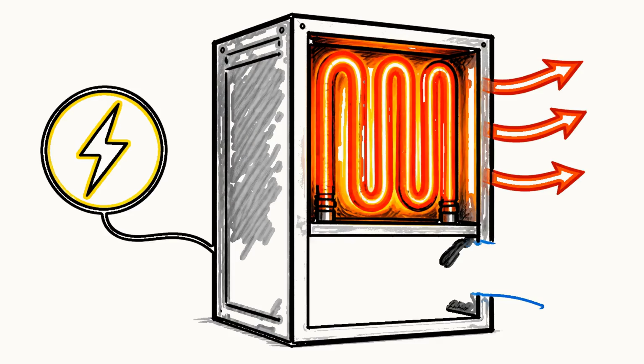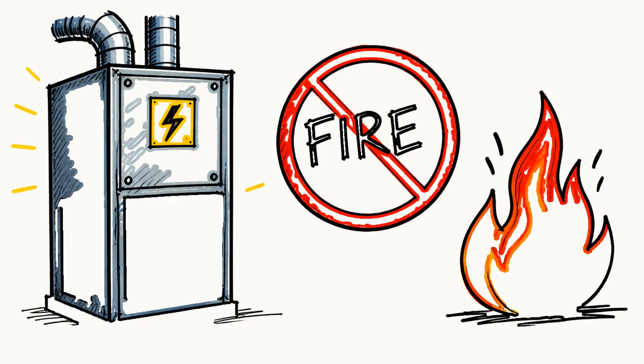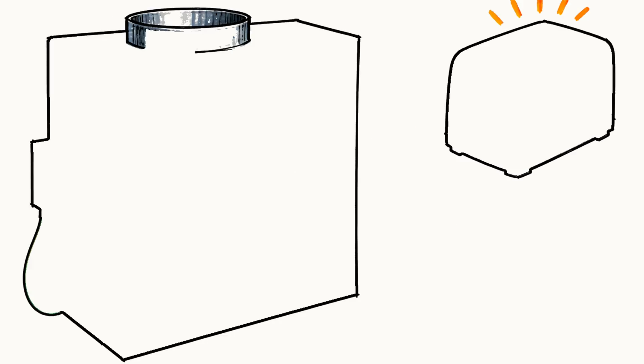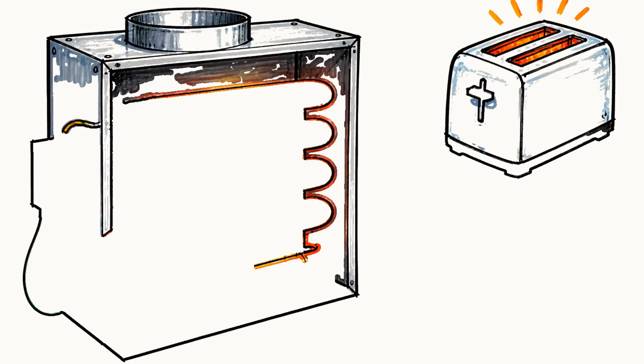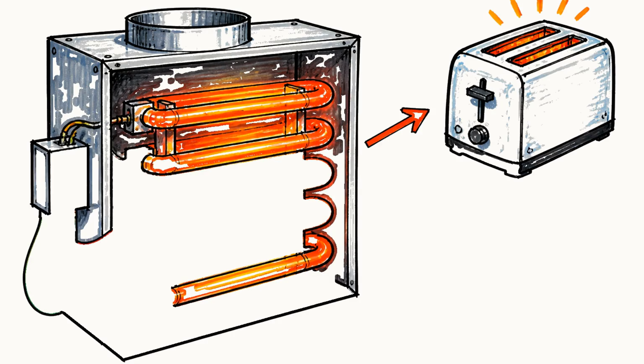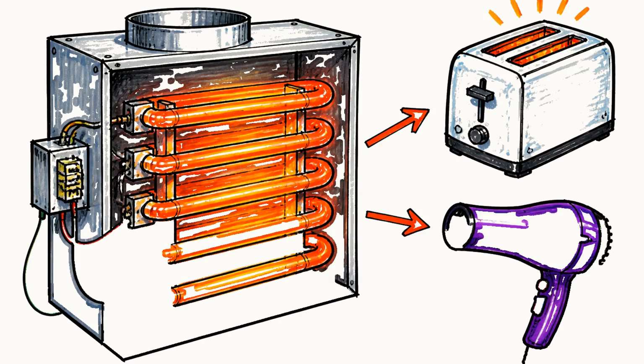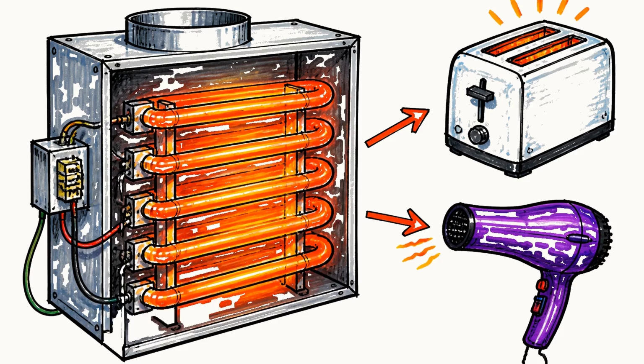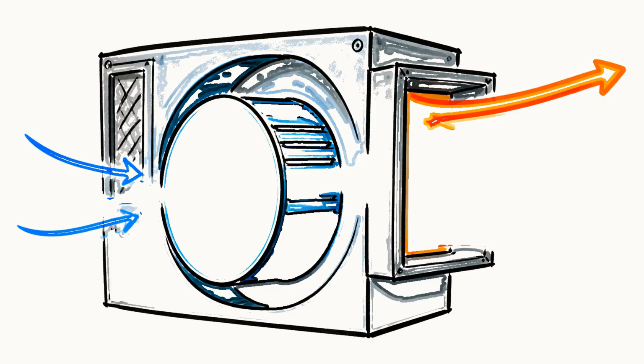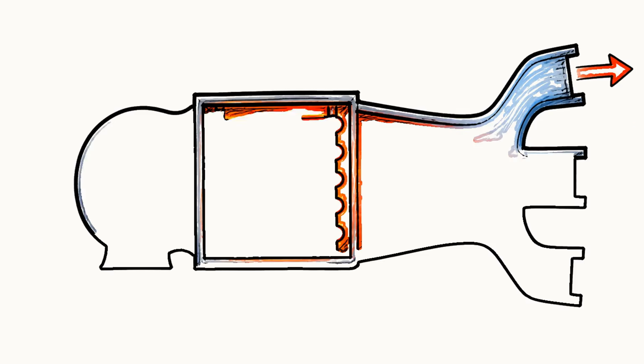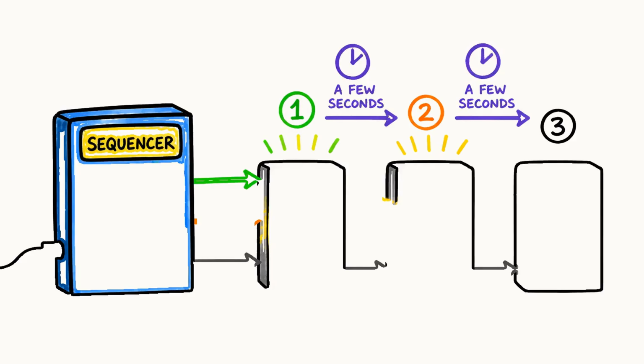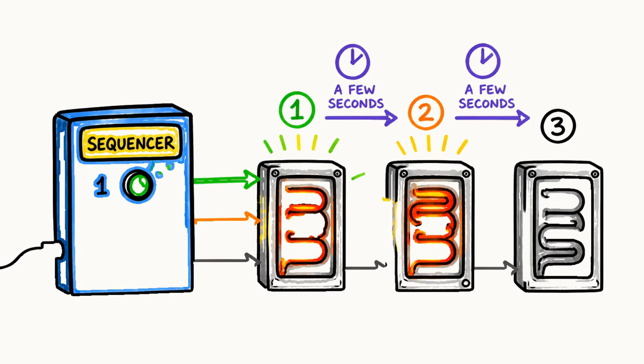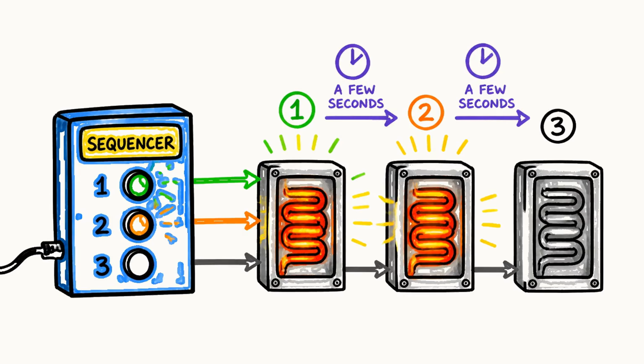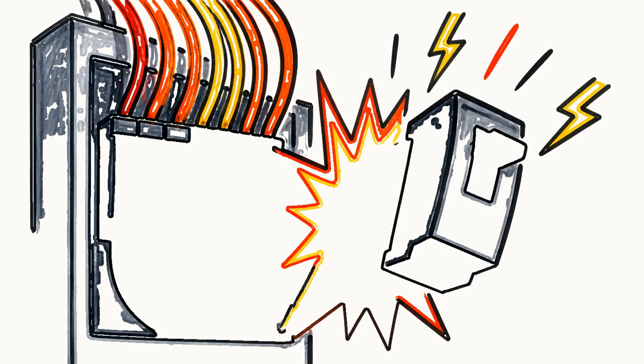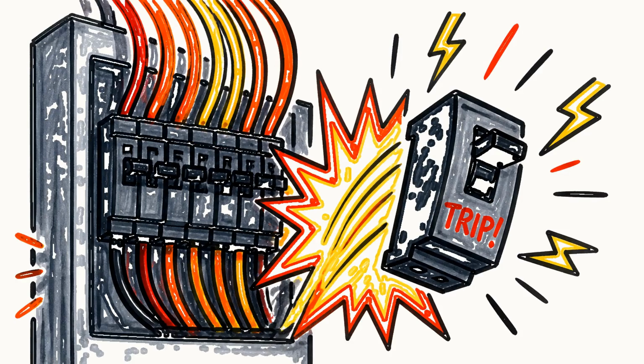Not every furnace burns gas, though. An electric furnace skips the fire entirely. Instead of burners and a heat exchanger, it uses thick metal coils that heat up when electricity runs through them, exactly like the elements in a toaster or a hairdryer, just much bigger. The blower still does the same job, pushing house air across the hot coils and out to the rooms. The clever part is a piece called the sequencer, which switches those coils on one at a time a few seconds apart rather than all at once. If they all fired together, they would yank so much power that they would trip your breaker.